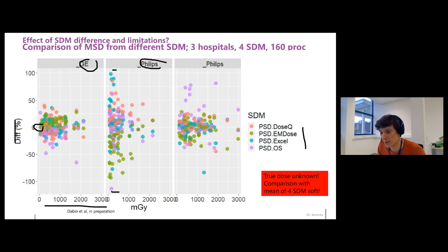It's not too bad. While for the Philips system, you can see in one hospital, there's a huge scatter. There's possibly 100% difference between the average skin dose estimate and the skin dose estimate from one system. And you can also see that some skin dose mapping software are more likely to over or underestimate. And in another hospital, you see that for the same angiographic units, the results are different again. So all those parameters are really important.